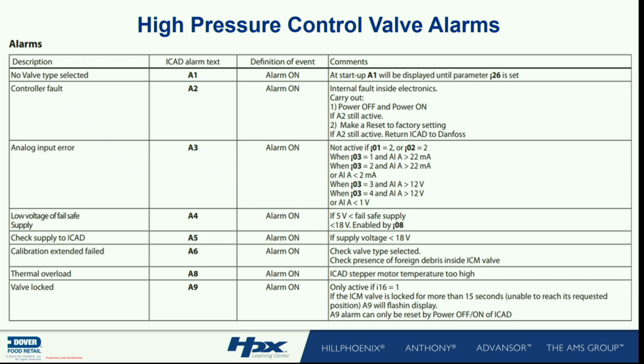Program and B—that's where we always want to go, but let's go old school a little. Remember I said there's a 0-10 volt signal coming from the controller to tell it how far to go? If it's 0 to 10 and that's 0 to 100, it's a nice linear number, yes? So I asked him, what is the voltage coming to the high pressure control valve? He said 10 volts, 100%. Help me—100%, how far open should the high pressure control valve be? 100%. Do you see how that's a valuable troubleshooting tool? Understand what the question is, yes or no? He was asking himself the wrong question, yes? He was asking me, why is the high pressure control valve at 100%? That's not the question, is it? The question is, why is he being told 100%? Two different solutions, yes?